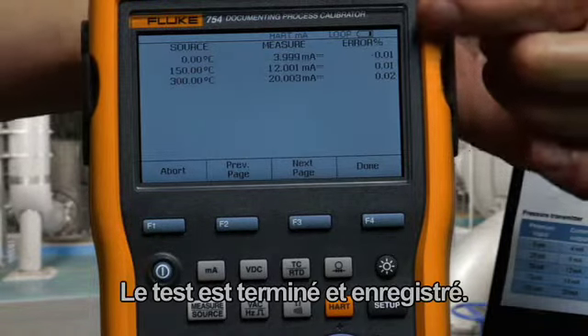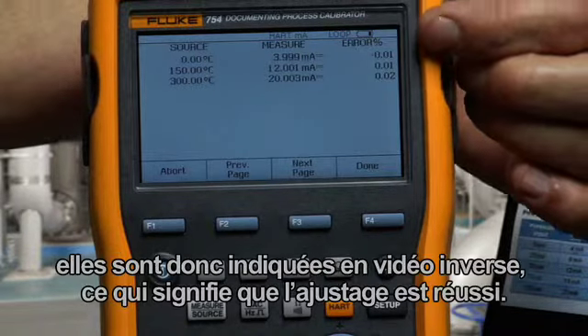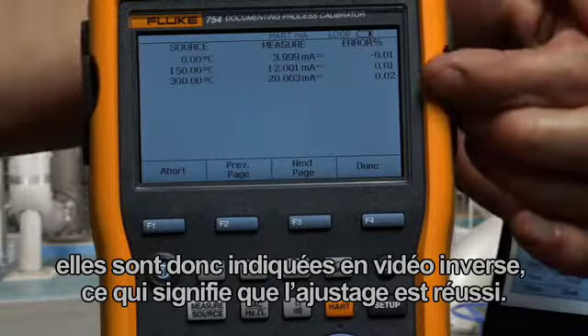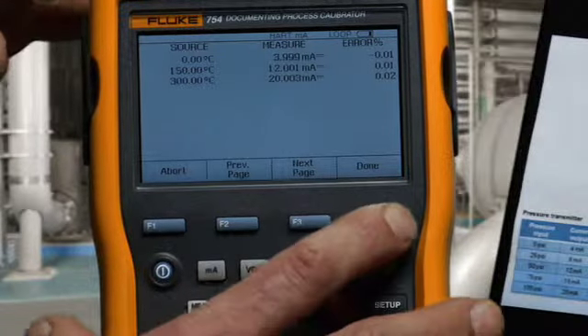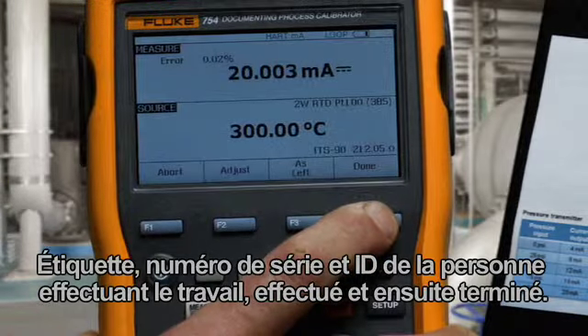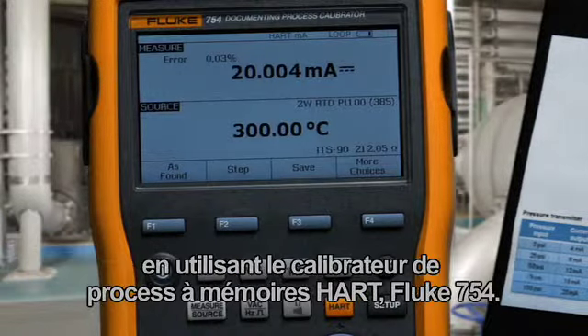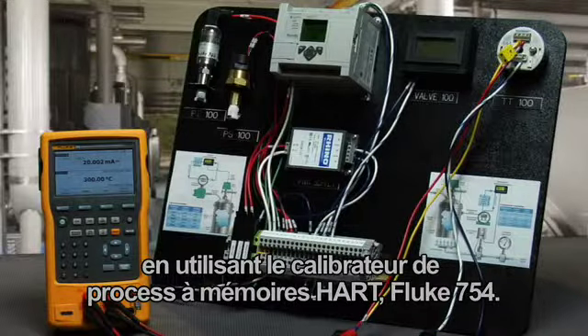Test is complete and recorded. All errors are smaller than the required test tolerance, so they're indicated in reverse video, indicating that the adjustment was successful. Tag and serial number and ID of the person doing the work. Done. That's how you calibrate a HART smart RTD temperature transmitter using the Fluke 754 documenting process HART calibrator.